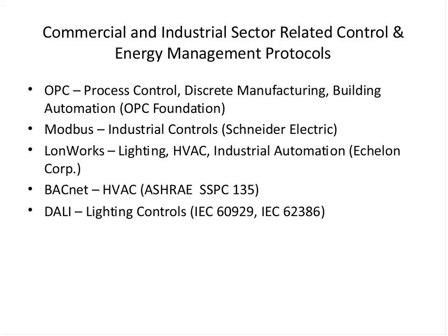So you basically have a very primitive application layer with very simple commands, because the types of devices that they're controlling are relatively simple. The things that they ask it to do: turn on, turn off, increase the voltage by this much, decrease it by this much, that's the type of SCADA that's going on for the most part. So for that level of sophistication, it's enough to have these standards with a serial interface. But increasingly, we're finding Internet protocol permeating into commercial and industrial, and as a result, we're increasing the ability of these protocols to do more stuff, to be able to control more devices, because an IP network can control more devices.